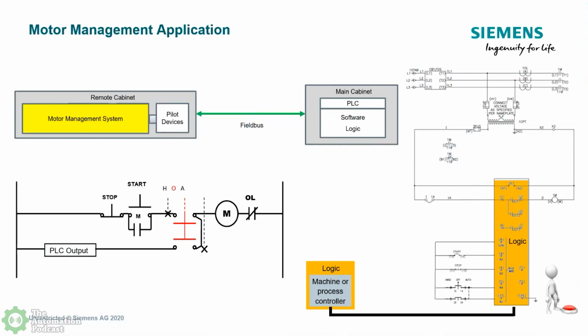It's kind of an eye chart, but what I want to emphasize with this is that with the SIMOCODE, it is your overload. It will measure your current, and if you want, it also will measure your voltage, so you can do phase loss or phase imbalance. But then it also has the ability to be your local control.